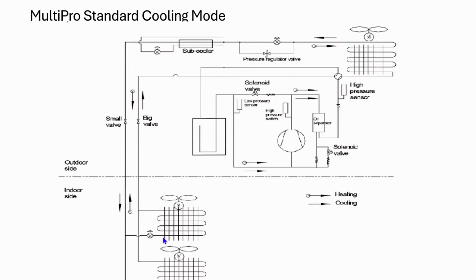Each one of these coils has an inlet and an outlet temperature thermistor. When you have the service tool hooked up, you can see the temperature of the outlet of that coil and the inlet of that coil right after your metering device. So if you're in cooling mode, that ought to be flashing off pretty good, and we ought to have a fairly cold input to that coil, right? Then as the refrigerant travels through the coil and absorbs heat, our leaving thermistor should be significantly warmer than our inlet, right? That's the data that I keep telling you guys the service tool will answer for you.